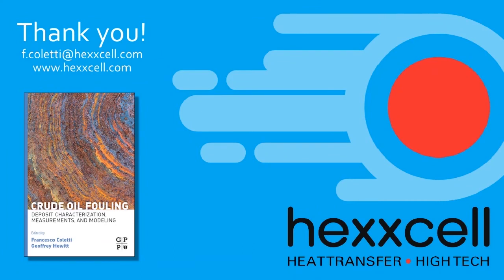Excellent. And we have a question coming through from Brunel. Is the fouling prediction data only compatible for shell and tube heat exchangers, or can it be transferred to different types of heat exchangers, such as plate heat exchangers or spiral heat exchangers? The answer is yes. It can be used in other types of heat exchangers. In the examples shown in the dynamic retrofit test, in fact, there were different types of heat exchangers. As I said, I cannot say which one is which, but definitely it can be applied to plate heat exchangers, twisted tubes, helical baffles, and so on. Excellent. Then we've got a question: what software have you used to do the optimization? We have our own internal software, so we developed our own algorithms, and we use our own algorithms for that.